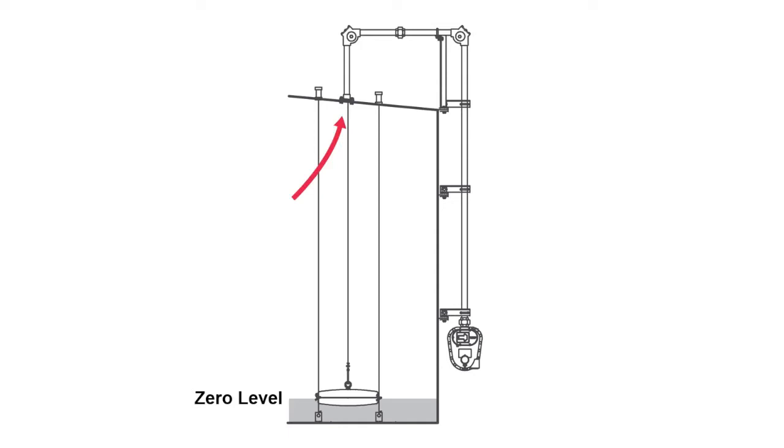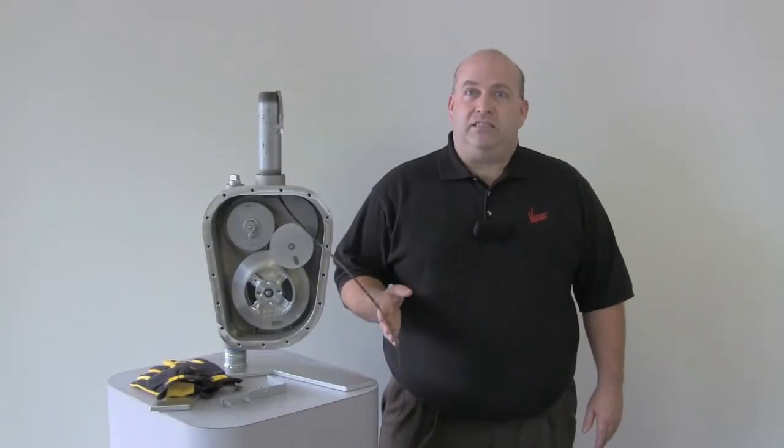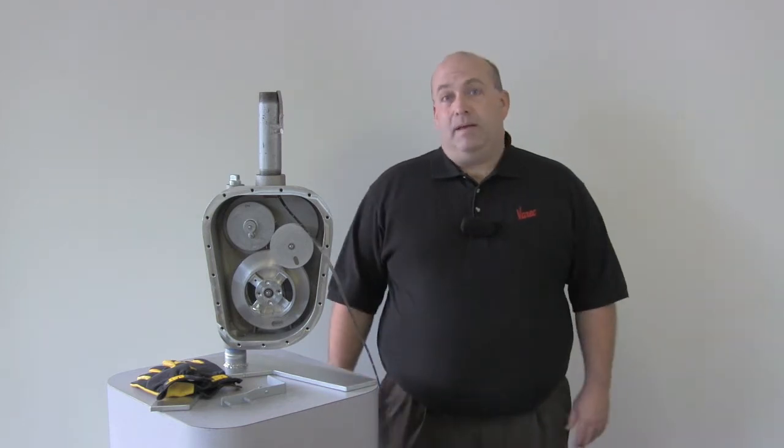We start this procedure with a float at zero level, an empty tank. The tape has been fed through the conduit and the gauge head and it has been cut so that we have about 6 feet of excess tape below the level at which the gauge head will be mounted.